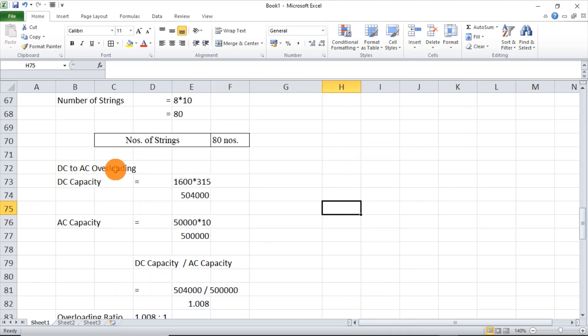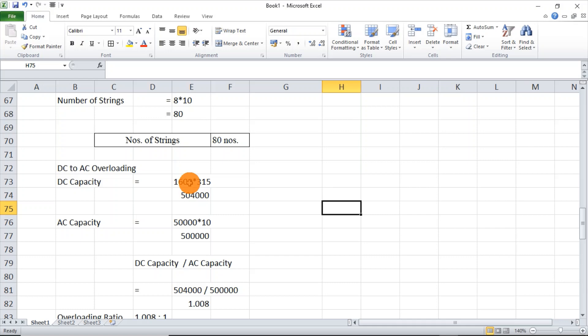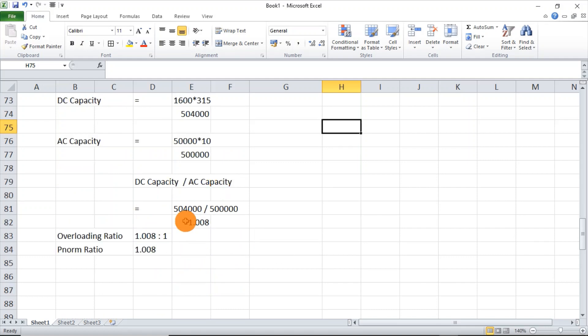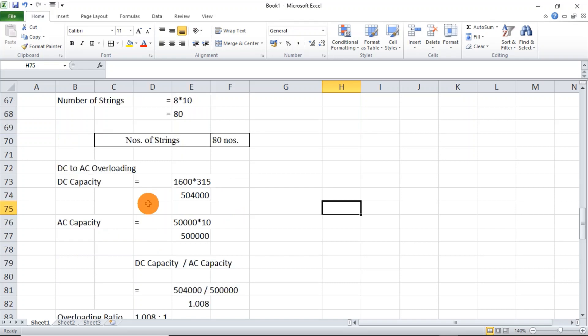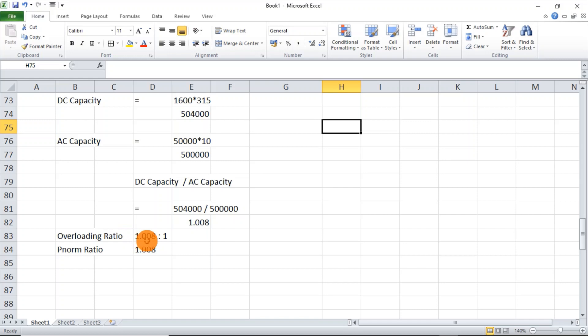Going to the DC to AC overloading: the maximum allowed overloading is 30%. For example, with a 10kW inverter you can connect up to 13kW of DC. In our system, the DC capacity is 1600 modules × 315Wp = 504,000W, and the AC capacity is 500,000W. So the DC to AC overloading ratio is 1.008 to 1, which is only about 0.8% overloading — well within the 30% limit.